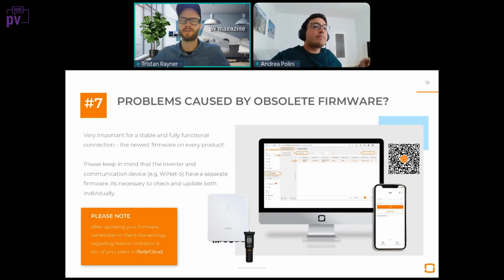Okay, yes. So we've already jumped across to the next one, which is problems caused by obsolete firmware. Yes, I would say this is one of the main issues we face when the whole Sungrow system is not working correctly or as the customer expects. This really may be due to the non-updated firmware of the inverter. So I highly recommend that every customer, as soon as they are experiencing some issue, first check if there is any firmware update available. And you can do this remotely, so without even going on site, if the installation is online.